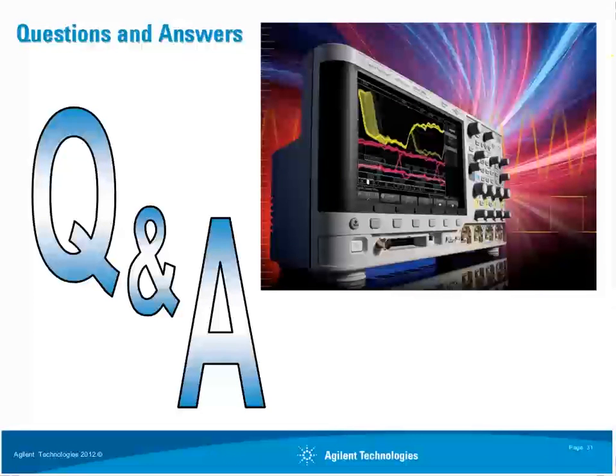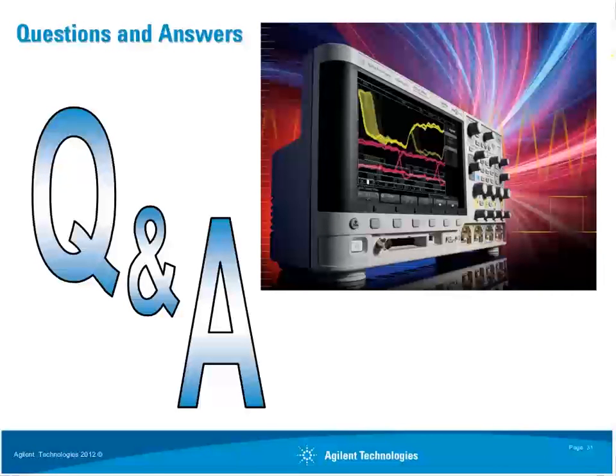Final question: You mentioned mask testing to reveal edge violations — how do you create the mask on the scope? Mask testing is a paid option. You connect your scope probe to a good signal on channel one, then within the mask testing menu, select Auto Mask and Create Mask. The scope software intelligently creates X and Y tolerances around the known good signal. You can also manually enter X and Y tolerances to create a custom mask. Using a known good signal is the quickest approach, but you can define masks using any tolerances you need.